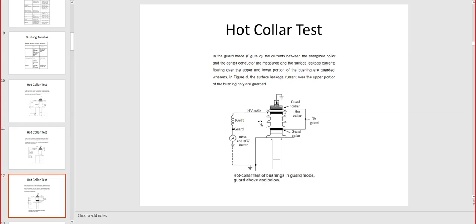Similar, this is another configuration that we can have for the hot collar test. Again, we have the millivolt meter, VA, milliwatt meter, and then same deal, we're gonna have a short cable that is connected to the collar, to the tap, that is for testing. And then in this case we have a bypass, a short between the two rings that are on the bushing, if they are available, and then we're gonna measure pretty much the C2 from that one to the ground, because this one is a short on the C1. So C1 is from the top to the actual tap, and then from the tap to the ground.